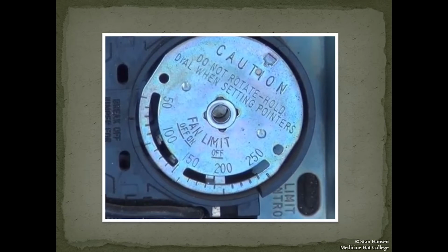The high limit control is meant to prevent a dangerous situation from developing, such as the plenum overheating due to a blocked duct or faulty blower. Its job is to shut off the burner. Typically, we use either disc type or spiral type, and it is placed in the furnace at the top of the heat exchanger. If you have a downdraft furnace, you have two high limit controls, one at the top of the furnace and also one inside the plenum.